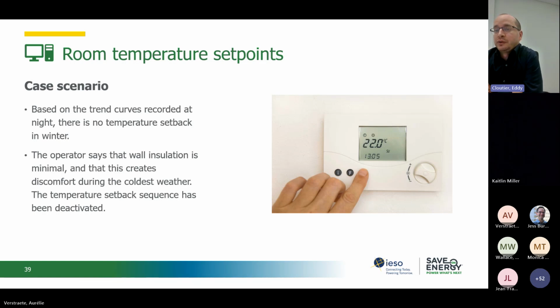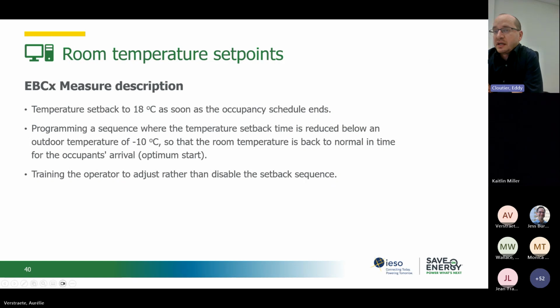A very simple scenario in that case: based on the trend curves recorded at night, there was no temperature setback in a specific building. And the operator said that the wall insulation was so bad that doing a temperature setback was creating a lot of complaints from occupants. So that was the reason why the temperature setback had been deactivated. Of course, it's a real concern having bad insulation in the walls, and it's true that it can create occupant discomfort because you will have very cold walls and it will create thermal discomfort. So the temperature was still set back to 18 degrees Celsius as soon as the occupancy schedule ends.